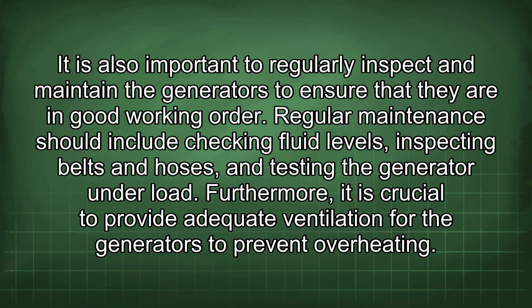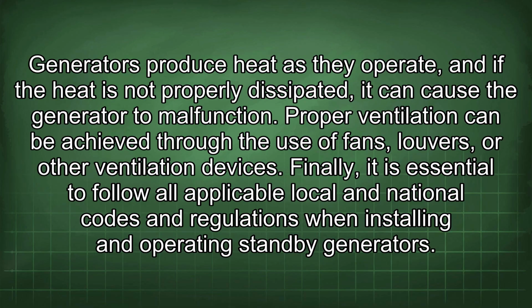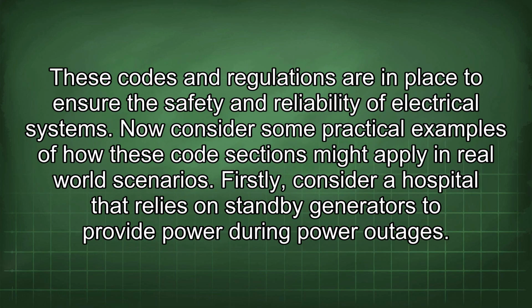It is also important to regularly inspect and maintain the generators to ensure that they are in good working order. Regular maintenance should include checking fluid levels, inspecting belts and hoses, and testing the generator under a load. Furthermore, it is crucial to provide adequate ventilation for the generators to prevent overheating. Generators produce heat as they operate, and if the heat is not properly dissipated, it can cause the generator to malfunction. Proper ventilation can be achieved through the use of fans, louvers, or other ventilation devices. Finally, it is essential to follow all applicable local and national codes and regulations when installing and operating standby generators. These codes and regulations are in place to ensure the safety and reliability of electrical systems.